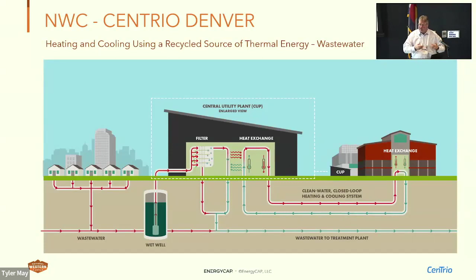So if we look at this, Brad showed you the pipe that was moved. Then we put in the waste screening system that keeps the solids out of the closed loop. Most of you are probably familiar with plate and frame heat exchangers, so we have those in the plant. We have one that separates the solids out, then we have three set aside in case we need to use the cooling towers, which are tied into the ambient loop.